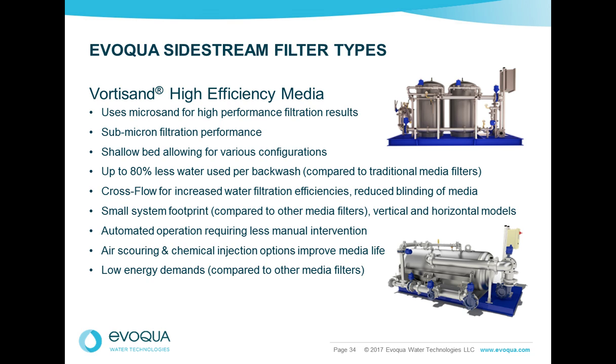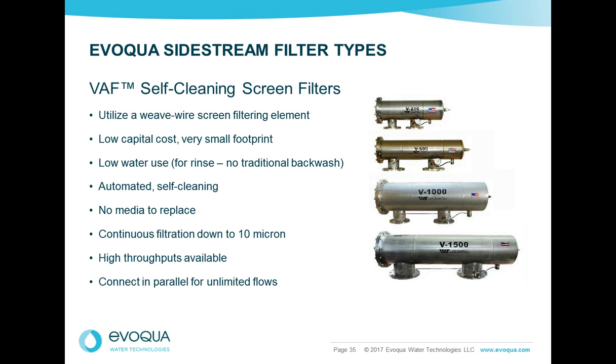The first is Vortisand, and Vortisand is a high-efficiency sand filter that uses microsand to provide submicron performance. It's got a shallow bed, and it reduces footprint and uses less water for backwash compared to other media filters. It's also got a low electrical demand, and it may help you qualify for some LEED credits for your facility. Since they work well in that 1 to 50 and 1 to 100 micron range, they're a great choice for most cooling systems.